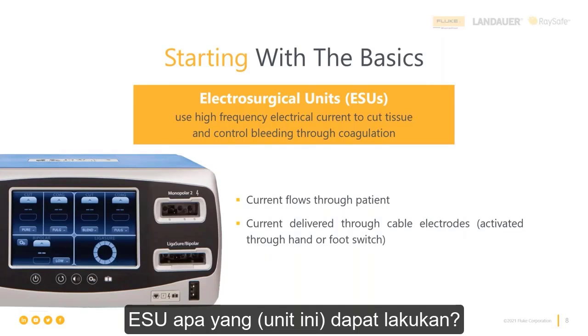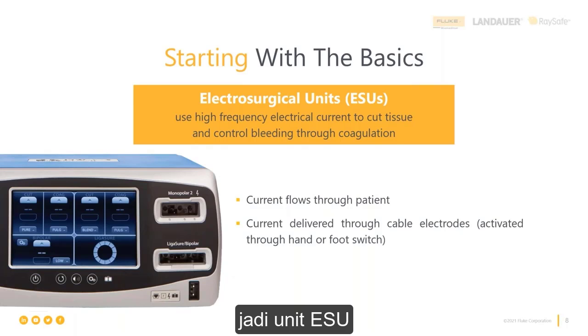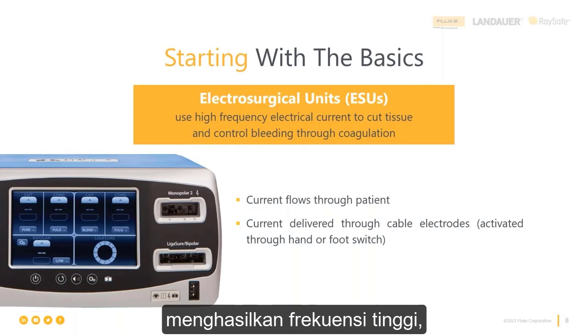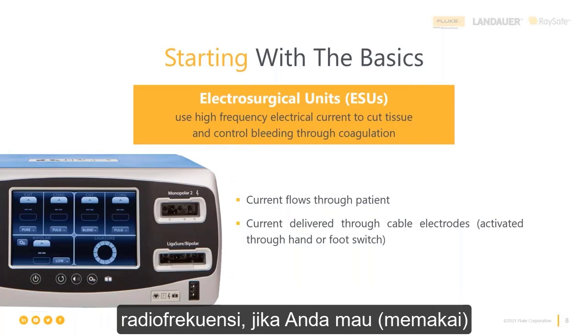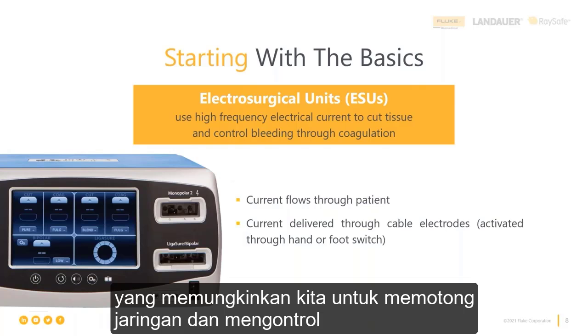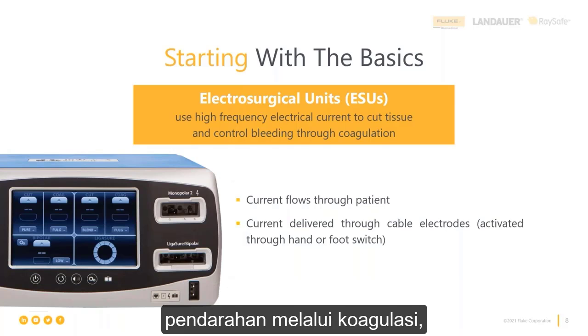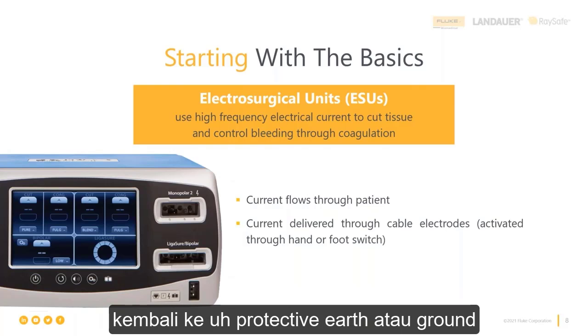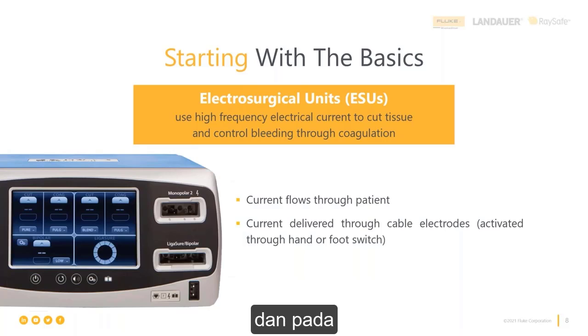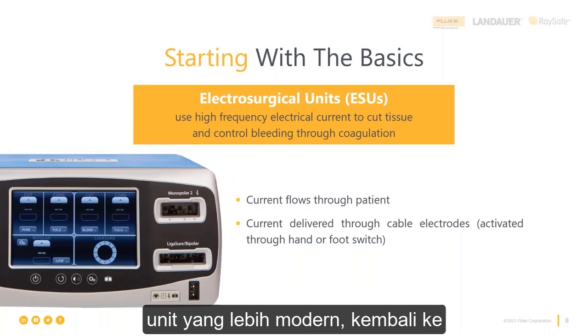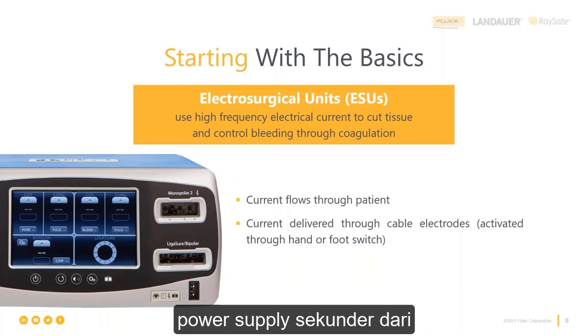What do they do? The electrosurgery unit produces a high frequency, radio frequency, electrical current that allows us to cut tissue and control bleeding through coagulation. The current flows through the patient from the generator back to the reference in the generator. Sometimes that will be back to protective earth or ground. In other units, the more modern ones, it's back to the secondary of the power supply of the electrosurgery unit.